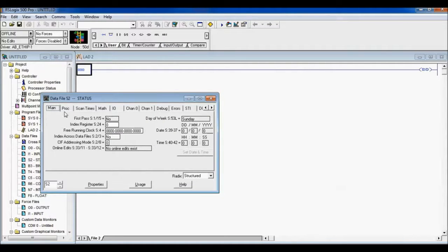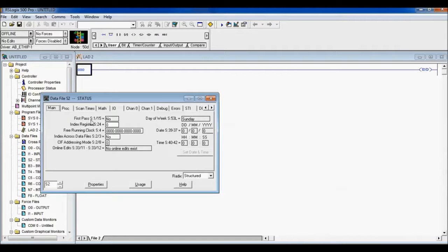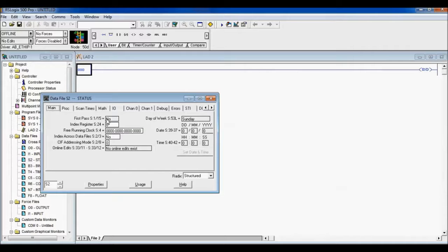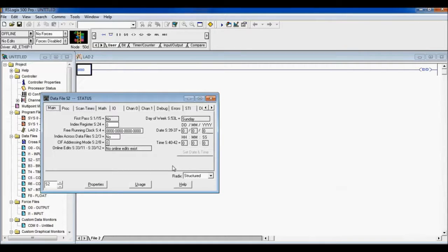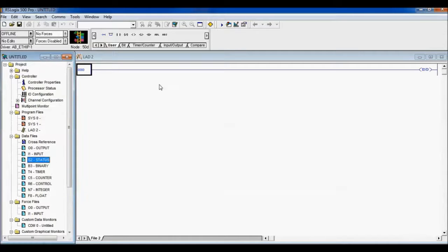The very first main one, you can see, is first pass: S:1/15. So that's your address. Any time you want to use a bit so that you know when the PLC has first powered up and completed its first pass, that's the bit you want to use. S:1/15 for this one.